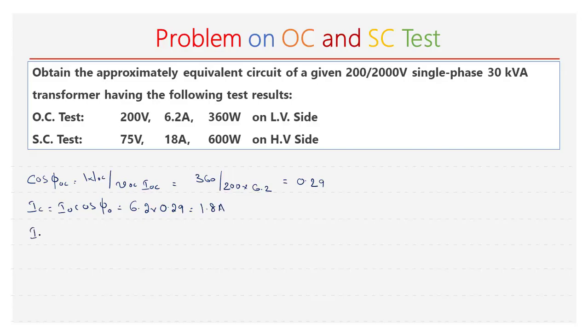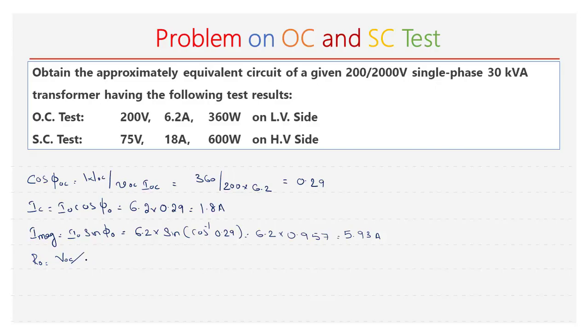R0 is equal to VOC divided by Ic, that is 200 divided by 1.8, which is 111.11 ohms. The magnetizing current Im is equal to IOC into sin φOC. Sin φOC is 0.95, so Im equals 5.93 amperes. Next, X0 is equal to VOC divided by Im, that is 200 divided by 5.93, which is 33.7 ohms.